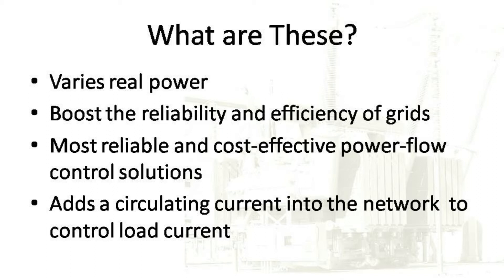The basic theory of achieving a phase shift is based on the relation between one phase section and another phase. We use delta connected winding to achieve the added delta voltage of 90 degrees, and this gives the easiest solution to achieve this phase shift. The phase shifting transformers not only boost the reliability and efficiency of grids by implementing or blocking loads, but also help grid operators get the most out of the infrastructure. They protect the lines, make the grids more stable, and reduce losses within our transmission system, and they are probably the most reliable and cost-effective power flow control solutions available.